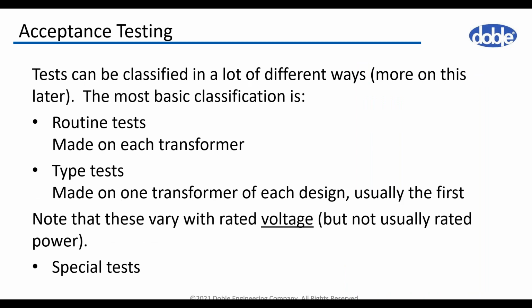We can classify the tests in various ways, but the most basic one is, let's say, routine, type, and special tests. The routine tests are performed on every single unit. Type tests are to prove the design and are performed on one unit. Usually this is the first unit if we have a series of a few, and they vary based on the voltage class of the unit. Special tests are a group of tests performed in addition to the routine and type tests, and agreed between the manufacturer and purchaser.